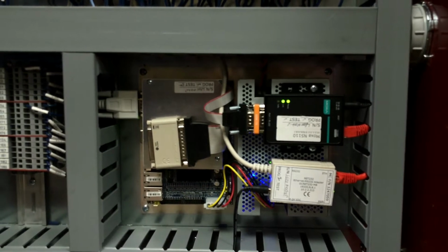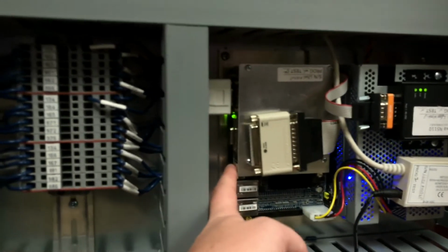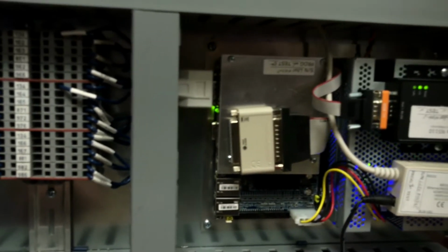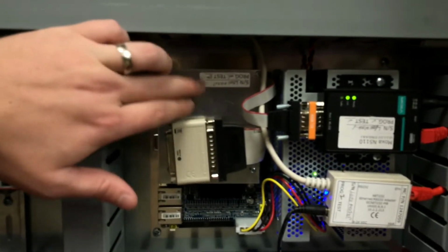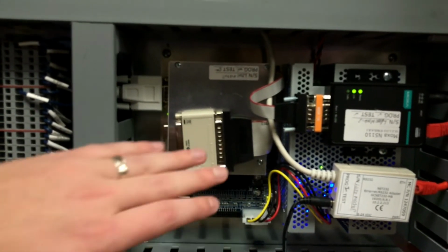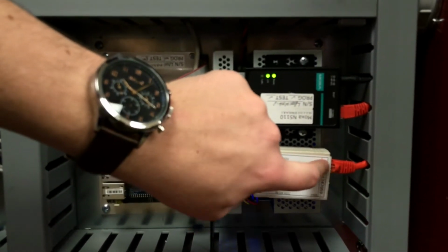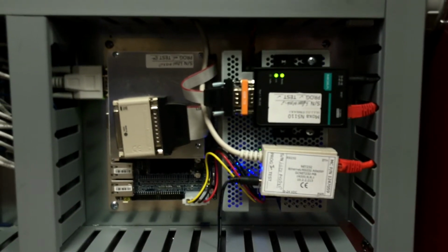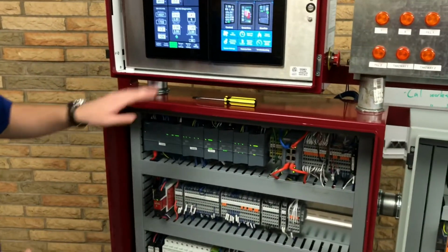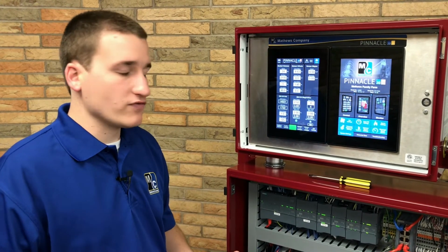One of the first things you can try to test the dryer master board: on the side, there's a small black button. Pushing that button will cycle power, and within a few seconds you'll hear a beep. That beep tells you that the dryer master board powered up, and it's likely that the dryer master board is working properly. Once you've heard that, you can look at the 232 and ensure that you have flashing LEDs where the Ethernet cord plugs in. If both of those things appear to be working, you can try replacing the cable, but if you can't get your heartbeat back, it's time to start replacing. We'd start with the 232 and go from there.